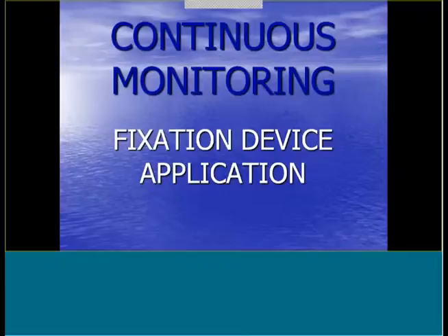Okay, so let's talk about applying the fixation device. Now, truthfully, honestly, it takes longer to put the headgear on and do all this than it does many times to do, say, a bubble study. The agitation just takes a few minutes and you inject, you're done. So a lot of times the whole setup takes a little bit longer to do than even the procedure itself. If you're doing a monitoring, allow yourself at least an hour to an hour and a half as far as time allotment.